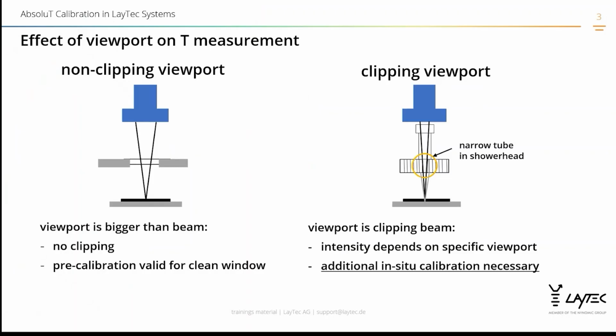Each and every one of your EpiTT and EpiCurve TT will be completely calibrated with all your parts. The full optical signal chain will be calibrated in front of a pre-calibrated German PTB or NIST standardized black body calibration source. And we will put all optical paths in the light path which are as close as possible to the real viewport tube holes as in your site. So in the best case, our pyrometer calibration will be accurate also in your real-world setup.